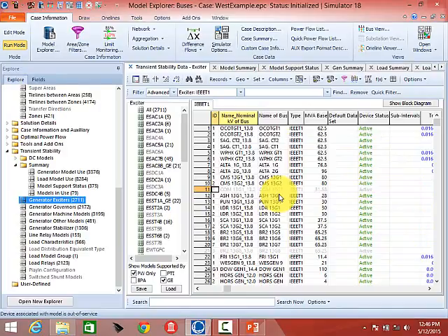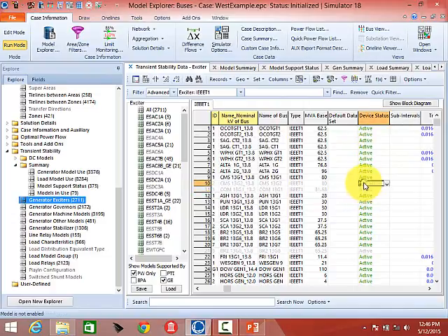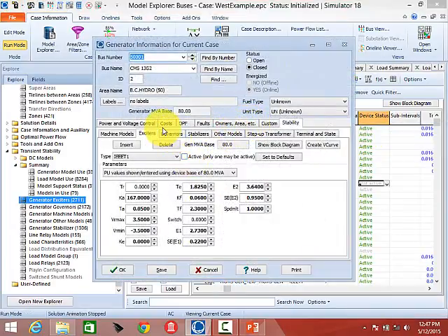The PowerWorld convention is that if fields are shown in blue they're enterable — you can directly enter values there. If an entry is grayed out, for example on the IEEE T1, that's because this model's generator is not in service. There is a Device Status field indicating whether that exciter is actually active. A generator can be out of service while still having an active exciter entry, but that exciter won't be included in the model.